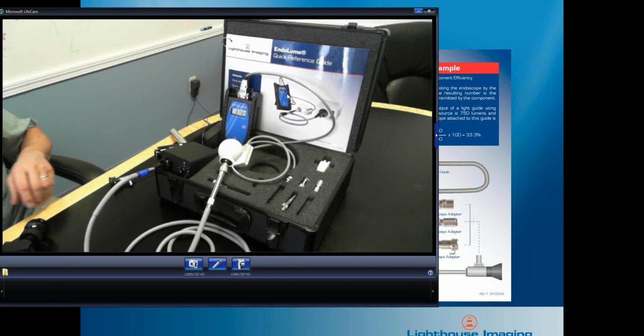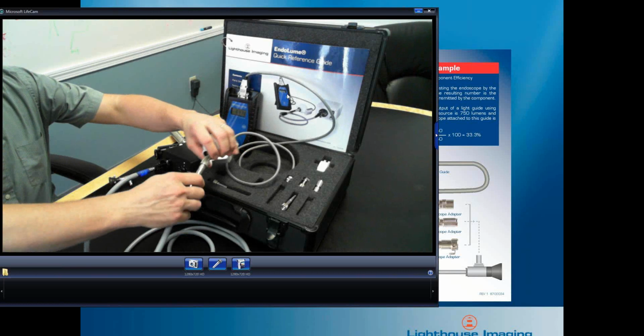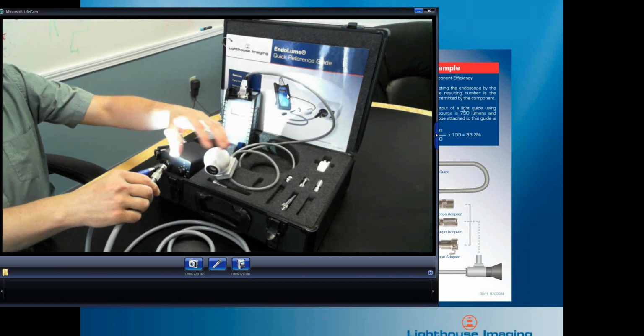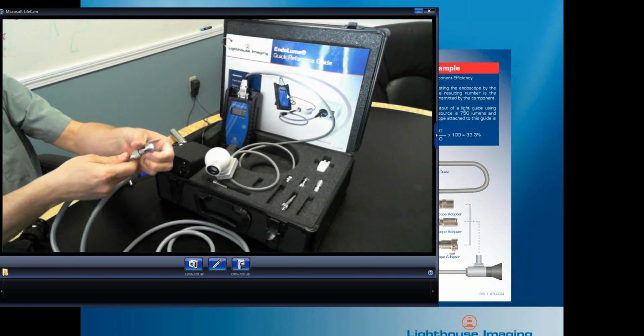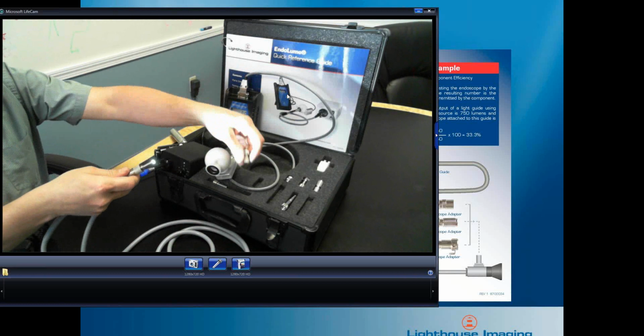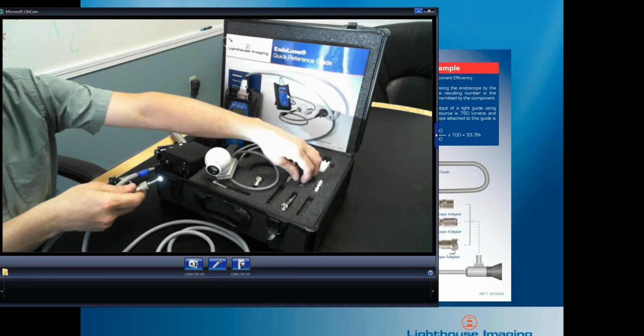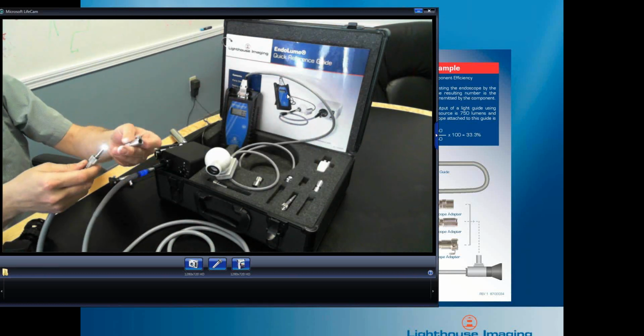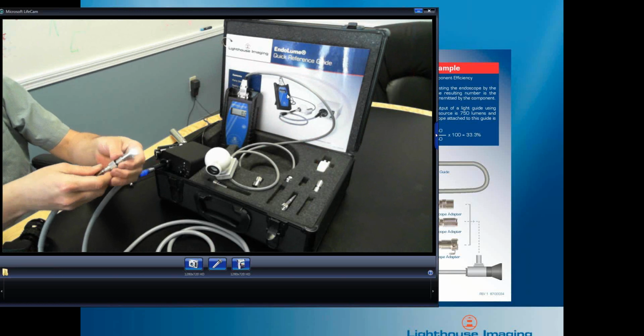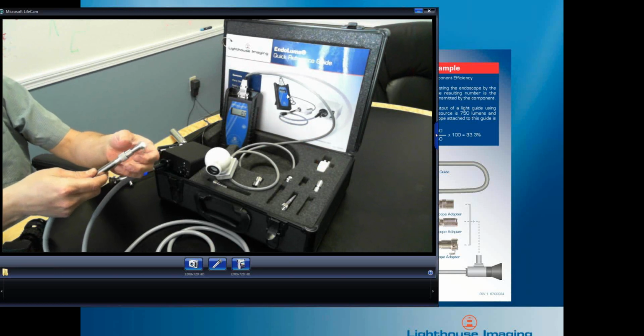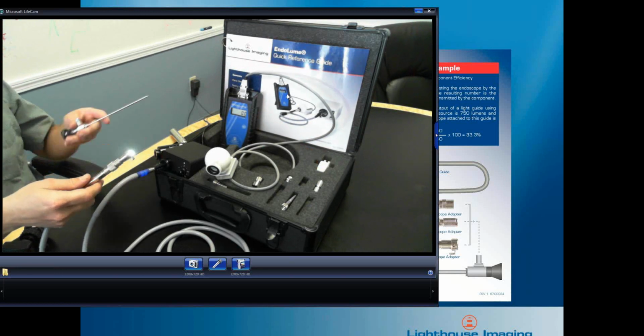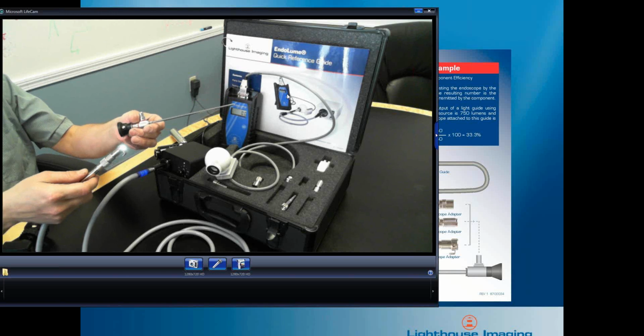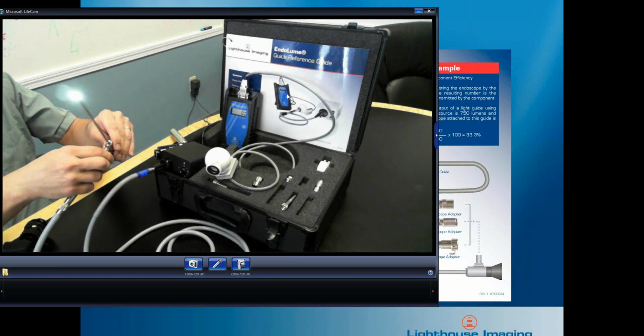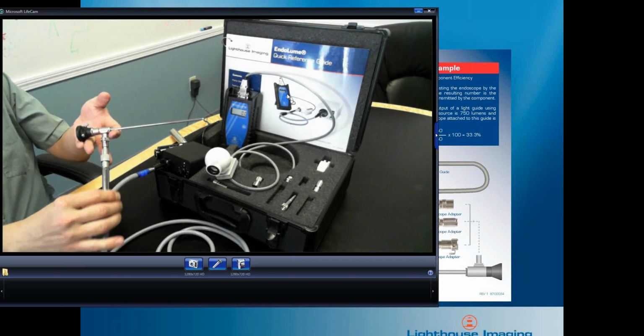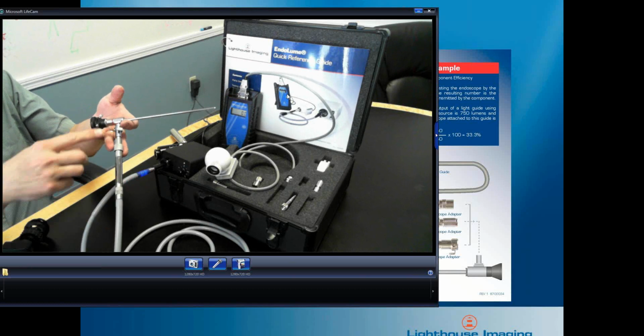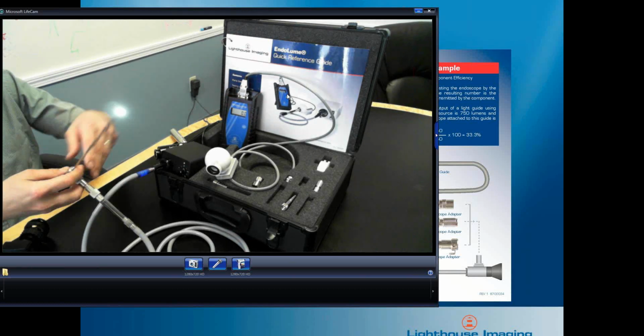So we'll switch back over to the live view. Now I will take my optical bridge out of the integrating sphere, and I'll take the integrating sphere adapter off, and I'll now use the correct fitting to go directly to the endoscope. I'll take my Richard Wolf arthroscope here, and I'll clip the cable onto it. So now I have the light source through the cable going to the scope.